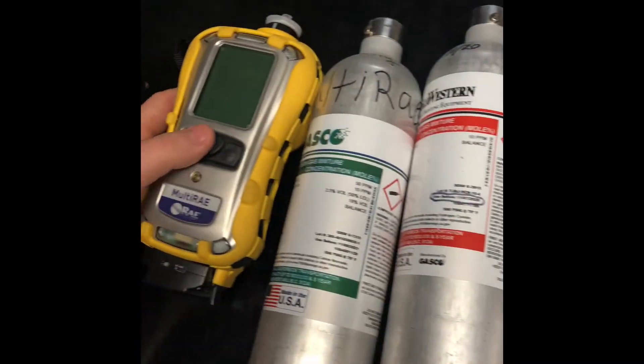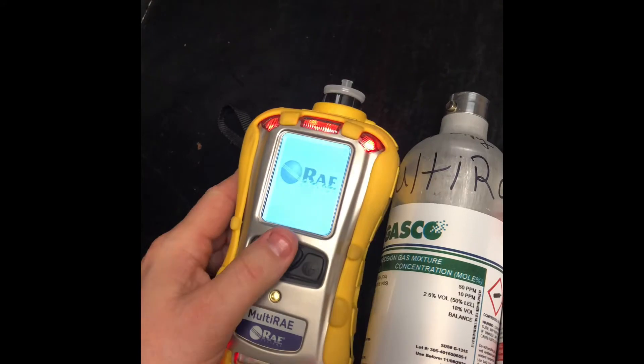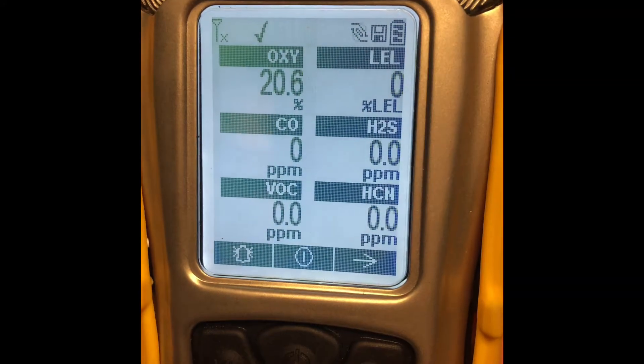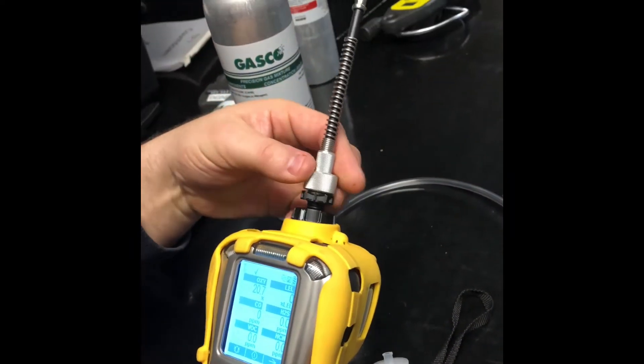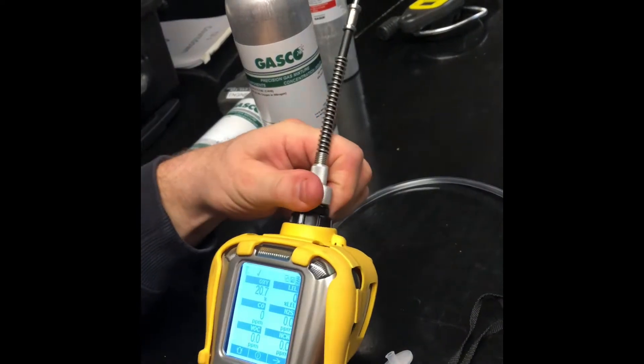Next step is to go ahead and power up your MultiRAE and let it go through the warm-up sequence. Take your MultiRAE, turn it on, let it go through the warm-up sequence, and you're going to unscrew your dust and water filter, attach your probe, assemble your cal gas and your regulator.